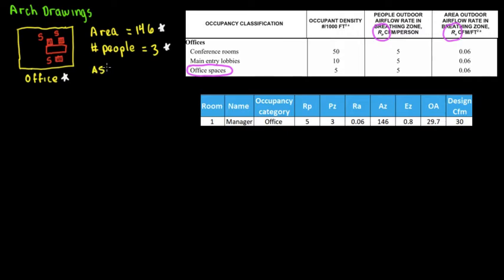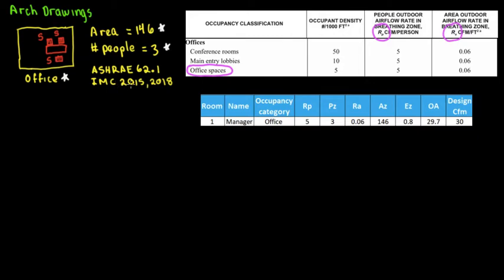ASHRAE 62.1 is for commercial, and number two — ASHRAE 62.2 — is for residential. So we're doing this for commercial purposes. This is also embedded into the IMC, whether the 2015 or 2018 edition — they are pretty much almost the same. You can always go online and find IMC 2015 or 2018 and go to chapter four, which covers ventilation. ASHRAE 62.1 is the standard, and the International Mechanical Code is the mechanical code depending on the jurisdiction or county.